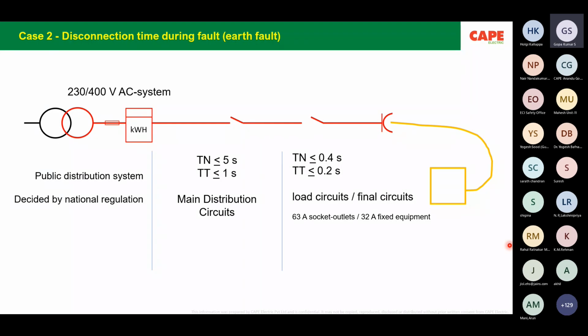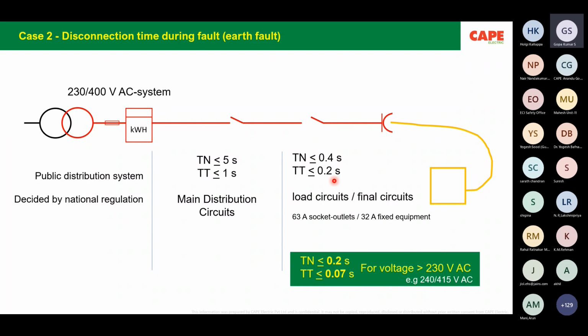So the disconnection time of an earth fault is very important, because if the disconnection takes more time, people may get electrocuted. In the picture, you have a transformer, you have a kilowatt hour meter, which is the point of commencement of supply, you have the fixed part of the installation, you have the final distribution circuit and a device connected to it. At the final circuit, for a TN system 0.4 second, TT system 0.2 second, TN 5 seconds and TT 1 second: these are the maximum allowed disconnection times in case of a 230 volt supply. Sometimes we also claim that our supply is 240 volt. In case of 240 volt, the disconnection times are even lesser.